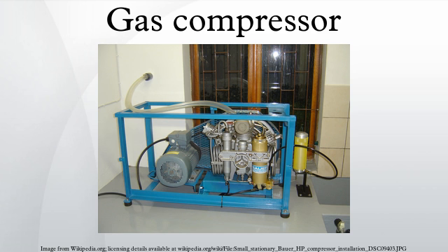Polytropic. This model takes into account both a rise in temperature in the gas as well as some loss of energy to the compressor's components. This assumes that heat may enter or leave the system, and that input shaft work can appear as both increased pressure and increased temperature above adiabatic. Compression efficiency is then the ratio of temperature rise at theoretical 100% versus actual. Polytropic compression will use a value of N between 0 and infinity. For the typical case where an effort is made to cool a gas compressed by an approximately adiabatic process, the value of N will be between 1 and K.